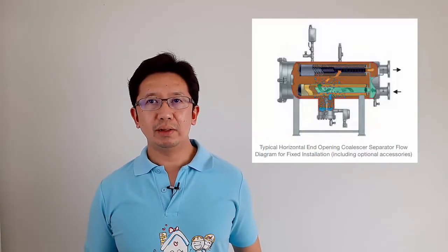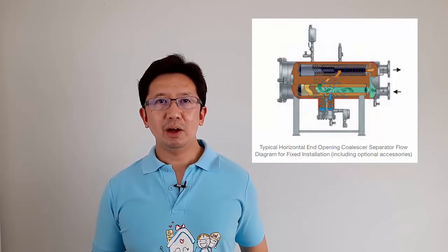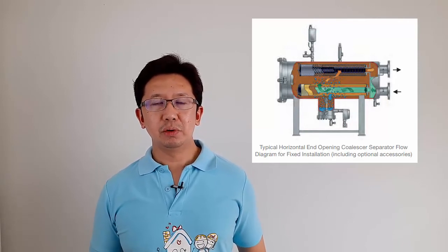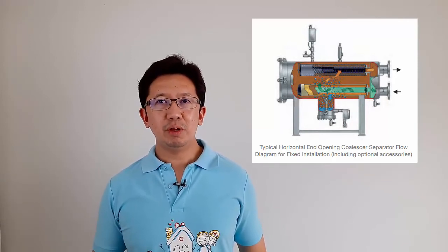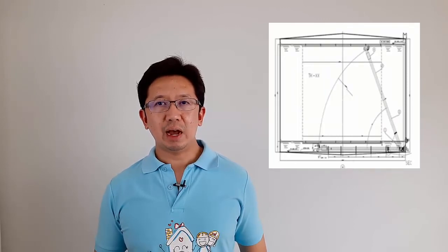What are the designs to prevent the water hazard to aviation? The first one is a water separator or coalescer, which is used to collect the water or other contamination before allowing only clean fuel to pass through. From the picture, the water will be collected from the coalescer boot. Second is the bottom cone design for the storage tank. The cone shape is designed to collect the fugitive water from the collector, which has a higher density, at the bottom. So to prevent the water contamination from carrying over to the jet fuel, daily manual draining by the operator is necessary.